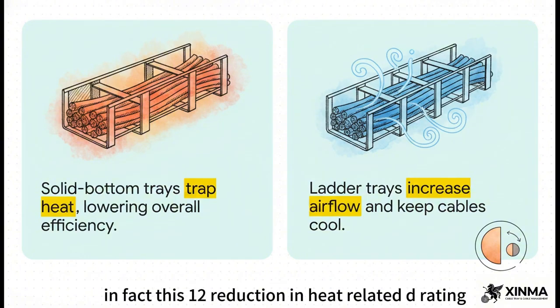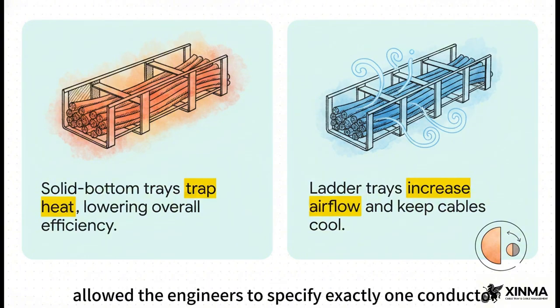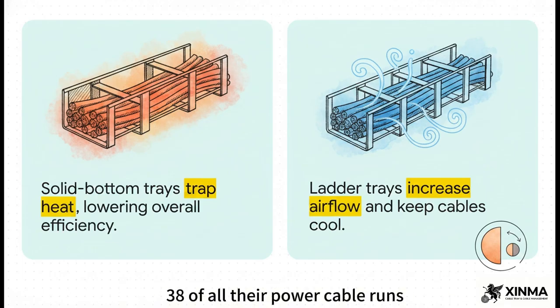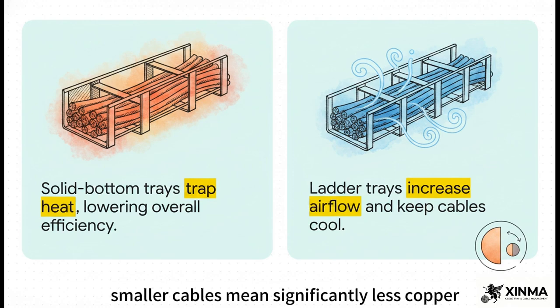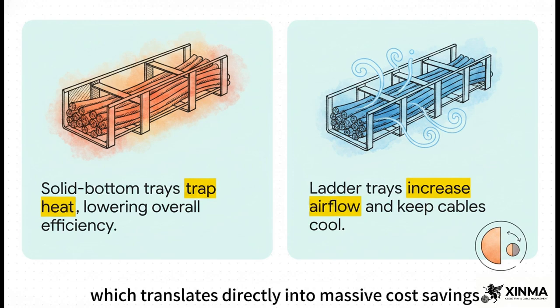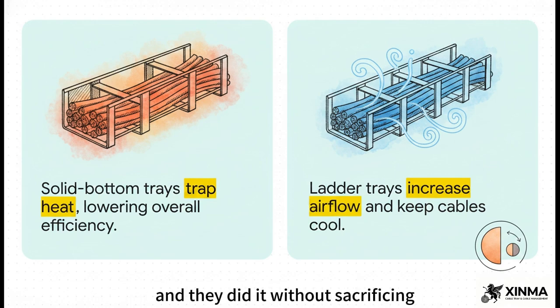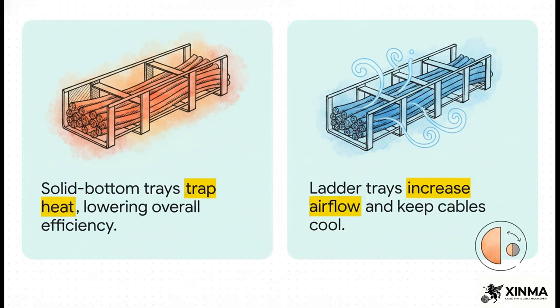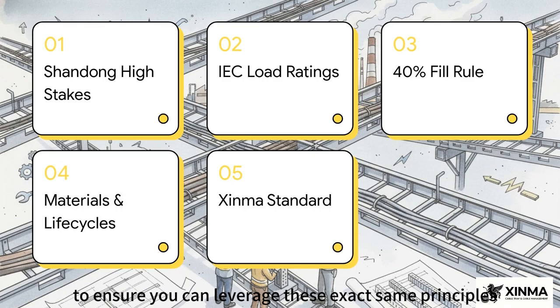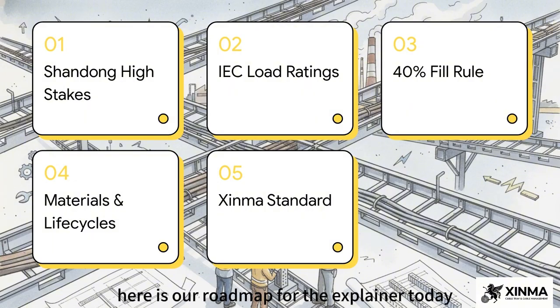In fact, this 12% reduction in heat-related derating allowed the engineers to specify exactly one conductor size smaller on 38% of all their power cable runs. Smaller cables mean significantly less copper, which translates directly into massive cost savings, and they did it without sacrificing an ounce of performance. To ensure you can leverage these exact same principles in your own designs, here is our roadmap for the explainer today.